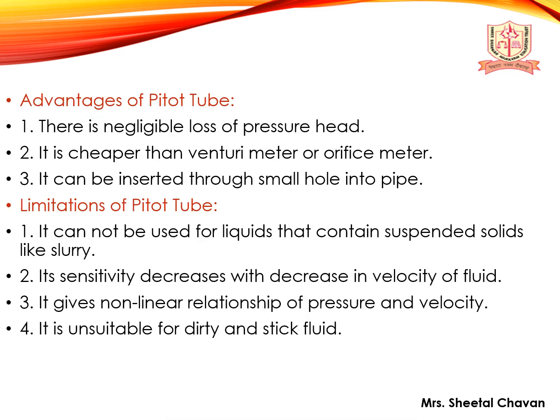Advantages of the pitot tube: negligible loss of pressure head, cheaper than the venturimeter or orifice plate, and can be inserted through a small hole into a pipe. Limitations: it cannot be used for liquids containing suspended solids like slurry, its sensitivity decreases with decreasing fluid velocity, it gives a non-linear relationship between pressure and velocity, and it is unsuitable for dirty and sticky fluids.